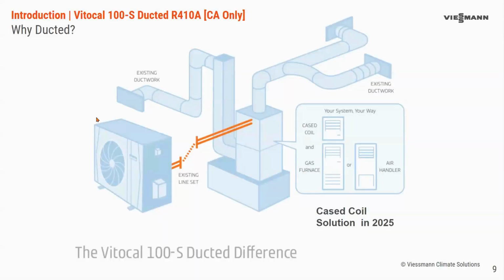Why would you go ducted? So this image here we use in our marketing kind of gives a good detail. You can reuse your line sets, reuse your duct work. In certain cases, if the indoor unit is compatible with the outdoor unit, you even are able to match this outdoor unit to an existing indoor unit. Of course, you have to check if you want an AHRI listed match. That's a conversation. However, the system is very flexible in how you can apply it. And you can use an air handler or a cased coil and furnace. So the cased coil is on the way to us.